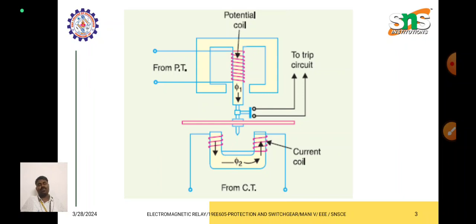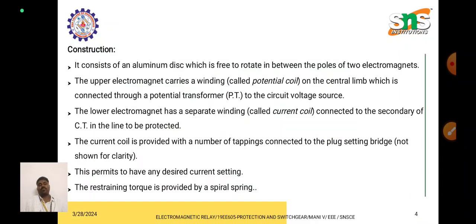If the aluminum disc rotates, the fixed contact and the moving contact touch. Because of this contact, we are able to trip the circuit breaker, so that we can disconnect the faulty section from the system. The disc is made of aluminum because of its low weight, so that it is free to rotate, and it is connected with a pivotal jewel bearing for smooth operation.